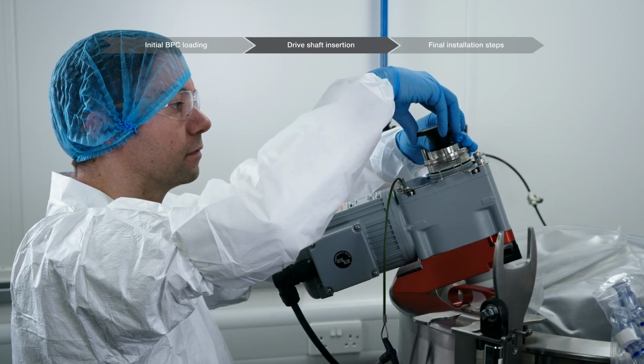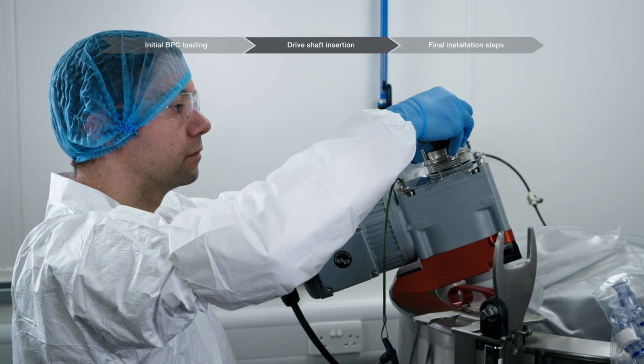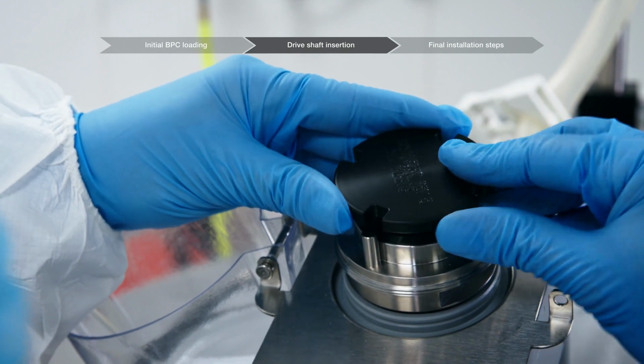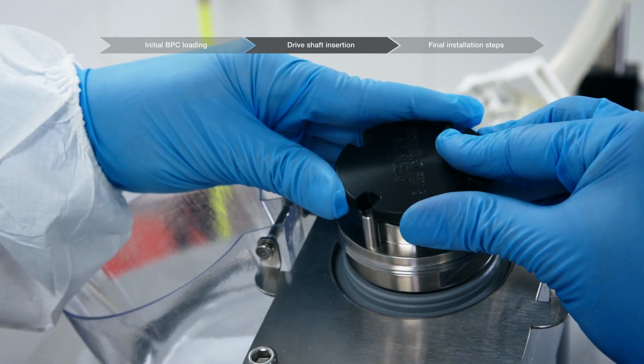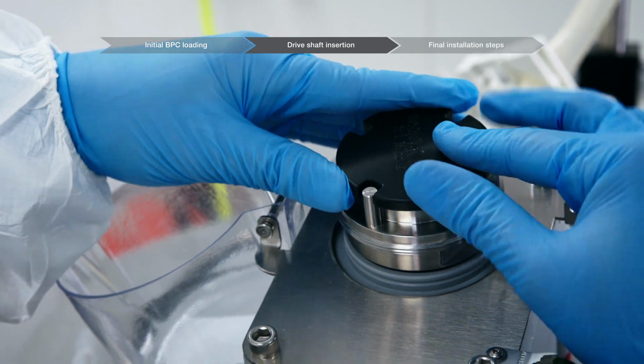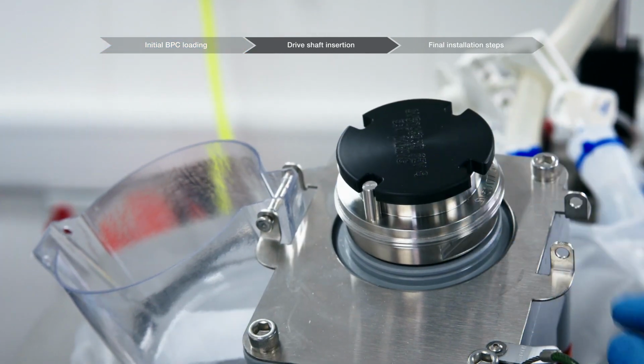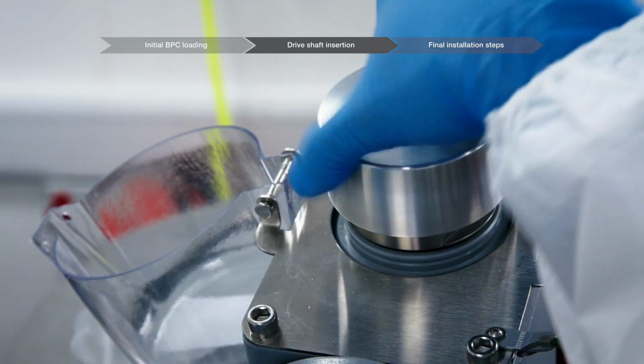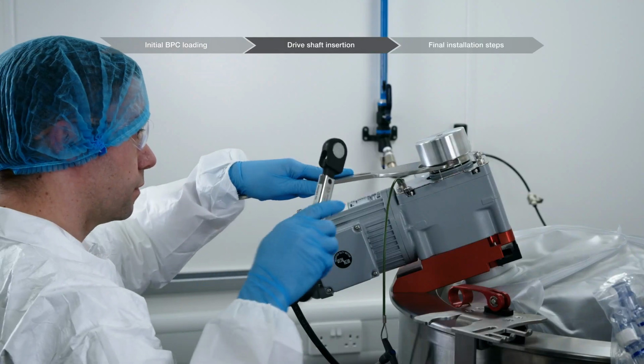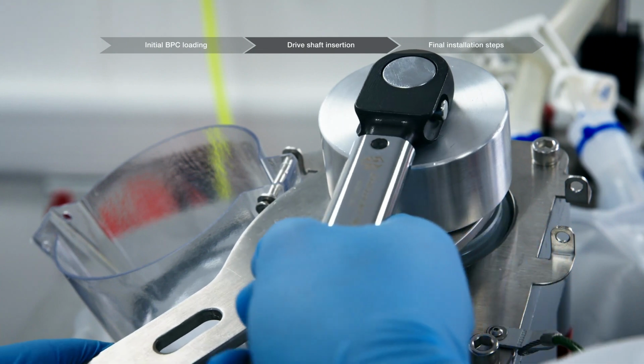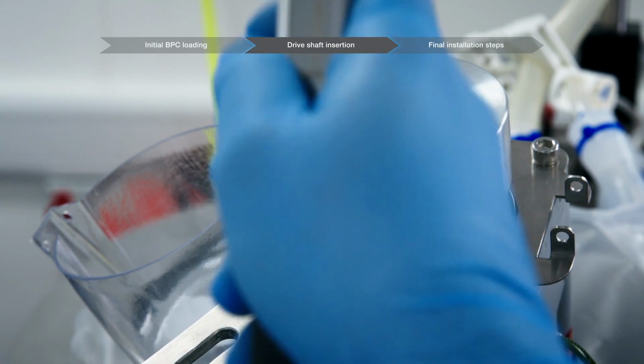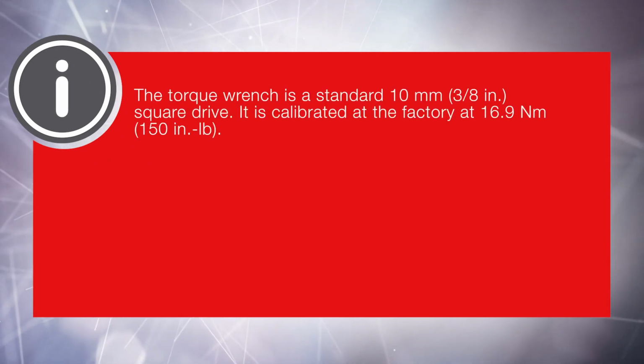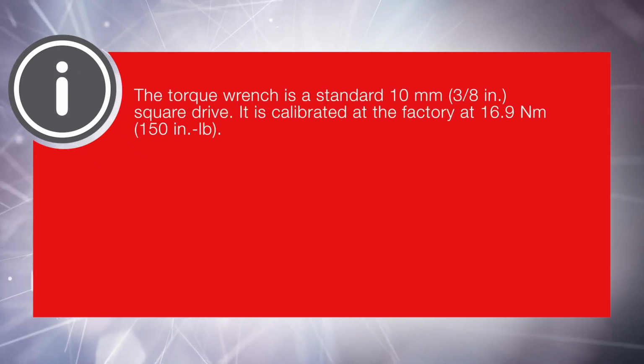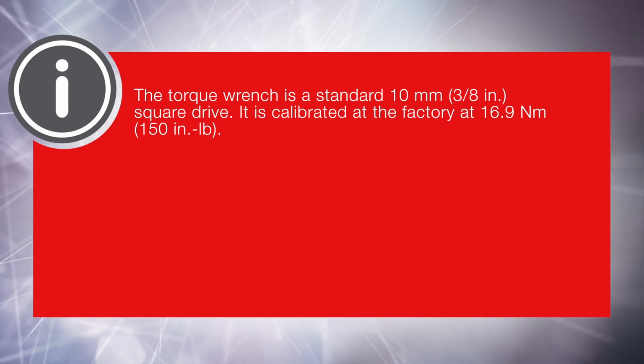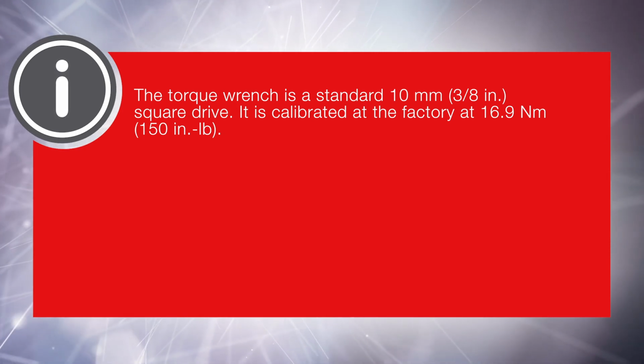When approximately 6 millimeters or 1/4 inch of the shaft remains, twist to align the motor drive keyway with one of the 4 outer slots on the drive shaft head. Directly couple the drive shaft to the motor drive. Place the motor cap on the hollow pass-through and hand tighten clockwise. Tighten the motor cap by placing the supplied spanner wrench on the hollow pass-through and tighten the motor cap using the supplied torque wrench. The torque wrench is a standard 10 mm or 3/8 inch square drive. It is calibrated at the factory at 16.9 Nm or 150 inch-pounds.